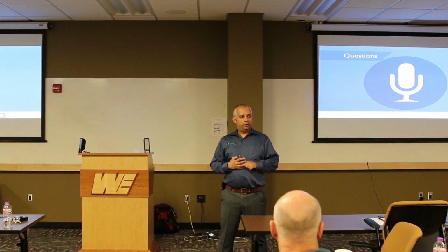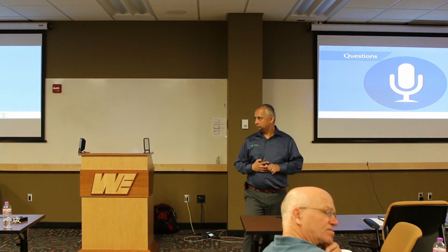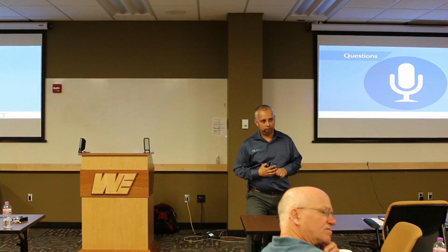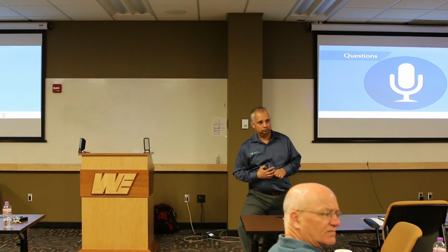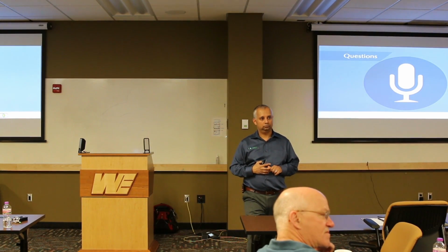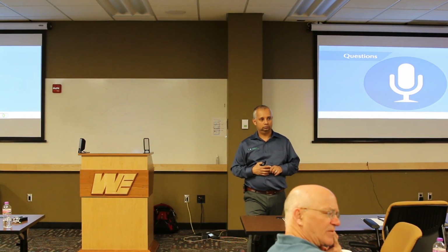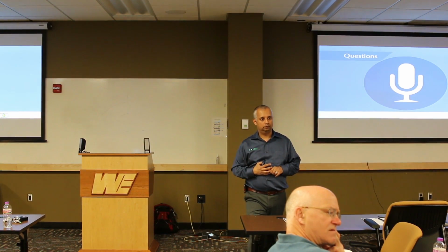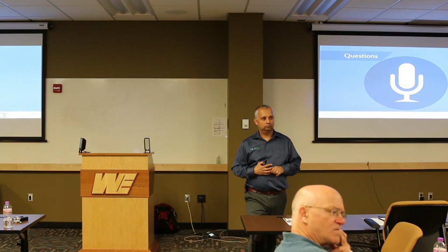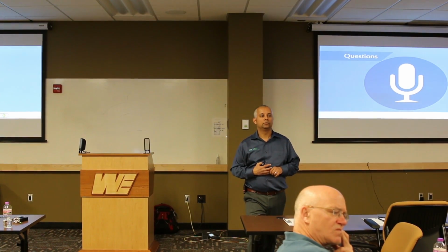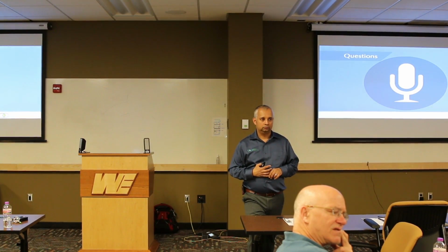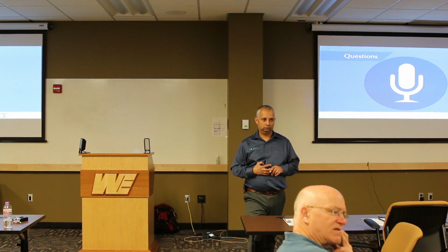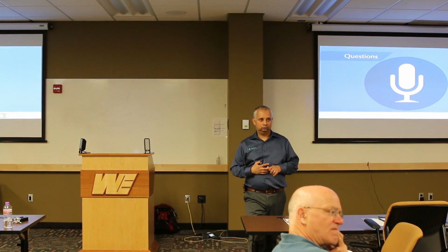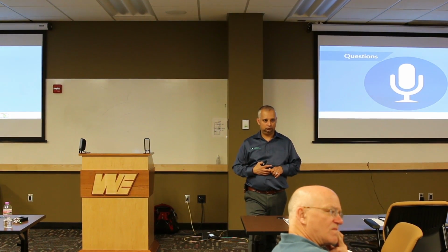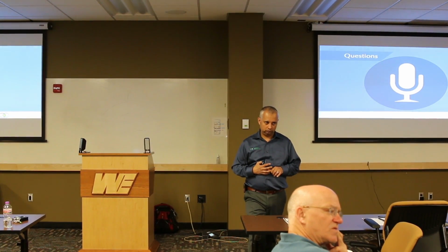I didn't think so. Yeah. Change breaker, change some of your MCCs, or you know, data. Just install the VFD. That all stays the same. It might, I believe it might make my hazard category lower because I've removed that motor load as a generator. If I've got the proper type of VFD, it's now eliminated that particular motor from the effects of feeding back into an arc.